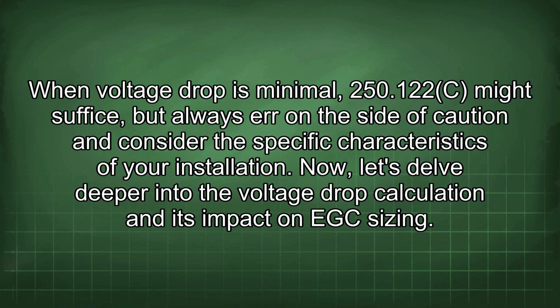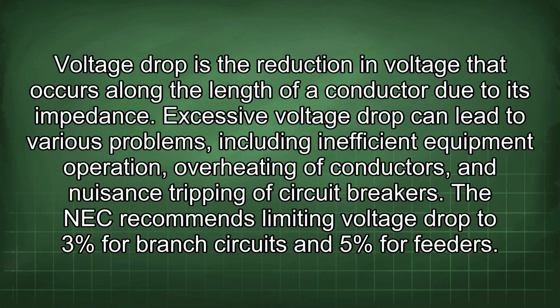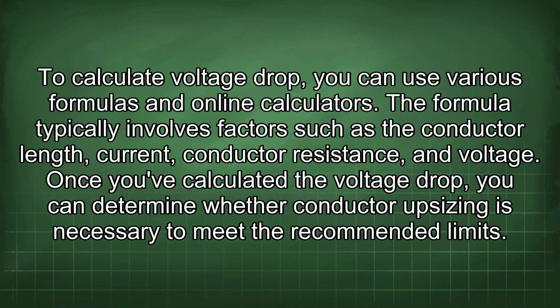Now let's delve deeper into the voltage drop calculation and its impact on EGC sizing. Voltage drop is the reduction in voltage that occurs along the length of a conductor due to its impedance. Excessive voltage drop can lead to various problems, including inefficient equipment operation, overheating of conductors, and nuisance tripping of circuit breakers. The NEC recommends limiting voltage drop to 3% for branch circuits and 5% for feeders. To calculate voltage drop, you can use various formulas and online calculators. The formula typically involves factors such as the conductor length, current, conductor resistance, and voltage.